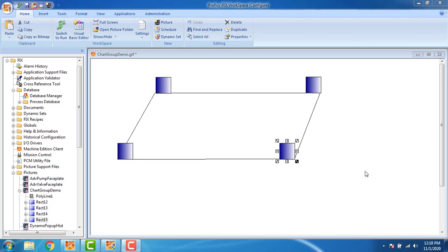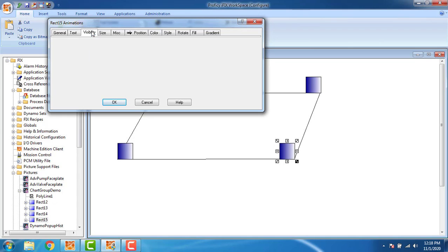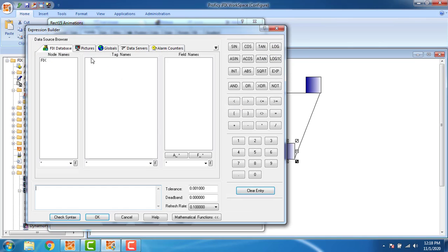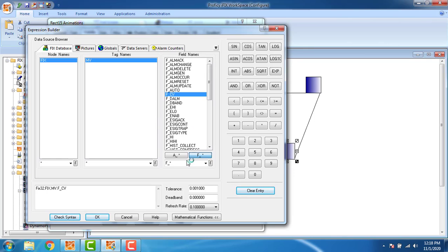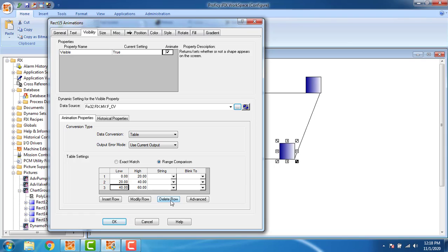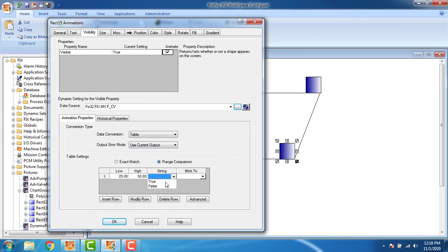Setting visibility for the second block: go to Advanced configuration, Visibility 'true', tag name is 'fixmvf.cv', click OK. Delete the other rows, use current output. The low value is 25 and the high value is 50 — up to that time it should be visible, so true. Click OK.